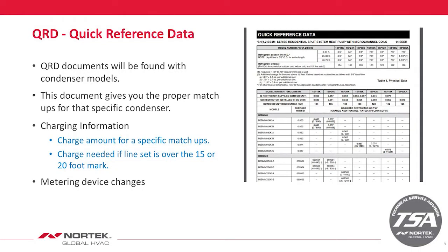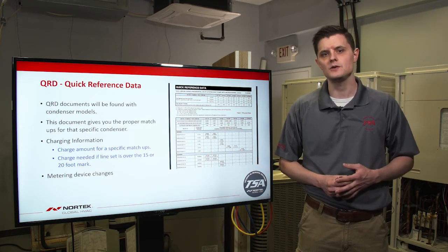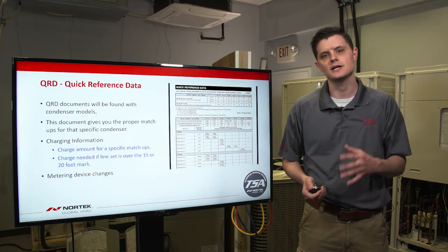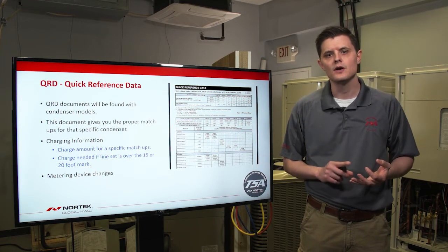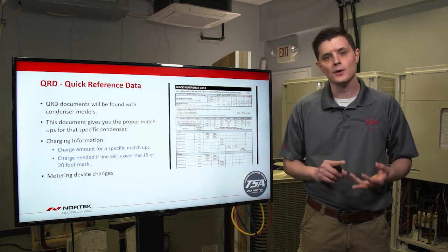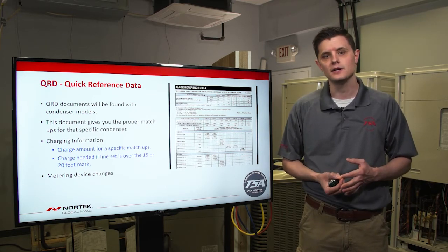We'll also list the additional charging amounts needed if your line set is longer than 15 or 20 feet. You want to look at the QRD for that specific unit to know whether or not it's pre-charged for 15 or 20 feet. On the QRD, you'll also find your metering device changes—most of the time this happens on piston-driven equipment, but depending on the model numbers you have upon install, you may need to change out a TXV on an evaporator coil. The QRD covers your matchup, extra charge needed, overall line set length, and any metering device changes.